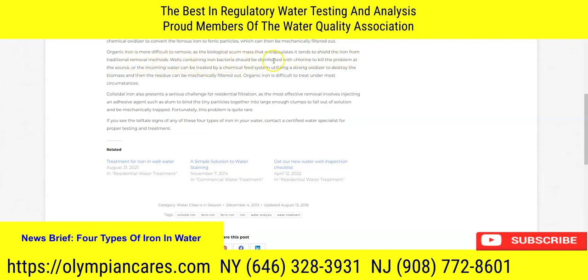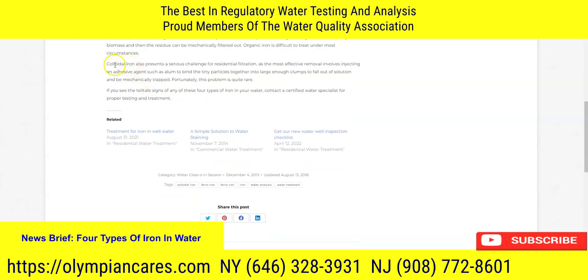Wells containing iron bacteria should be disinfected with chlorine to kill the problem at the source, or the incoming water can be treated by a chemical feed system utilizing a strong oxidizer to destroy the biomass, and then the residue can be mechanically filtered out. Organic iron is difficult to treat under most circumstances. Colloidal iron also presents a serious challenge for residential filtration, as the most effective removal involves injecting an adhesive agent such as alum to bind the tiny particles together into clumps large enough to fall out of the solution. Fortunately, this is quite a rare problem.